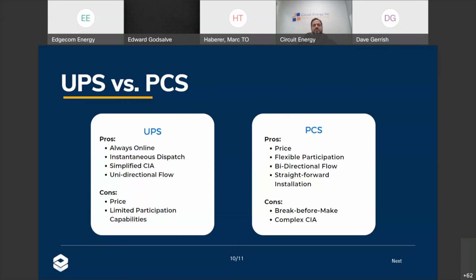It's instantaneous dispatch, meaning our network operations center can bring on the UPSs and connected batteries as quickly as electrons move. It has a simplified connection impact assessment process, since we don't have to provide many details to the utility or local distribution company about how the system is set up, because it's only a unidirectional feed, there's no way for us to inject energy back onto the grid. That's one of the biggest advantages of UPS, especially when dealing with a utility that's not a fan of distributed energy resources. But on the other hand, it's more expensive and also limits your participation ability.